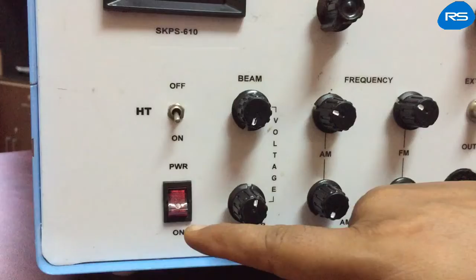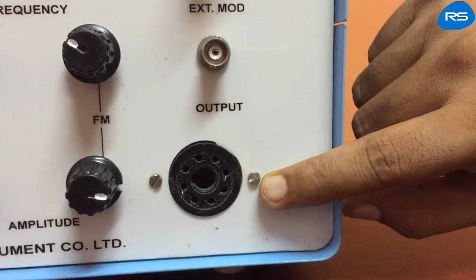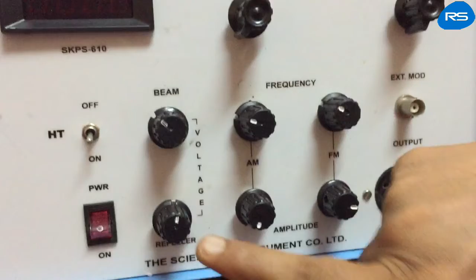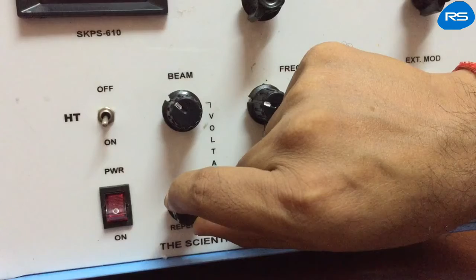This is your power switch to turn the instrument power on and off. This is our output octal socket, which is matched with the octal plug of the Klystron mount and provides all voltages which are required to operate the Klystron tube. The beam voltage: when rotating in the clockwise direction, it increases the beam voltage, which can be read on the panel meter. Repeller voltage varies the reflector voltage, which is used to obtain different modes of the Klystron or to optimize the power output.